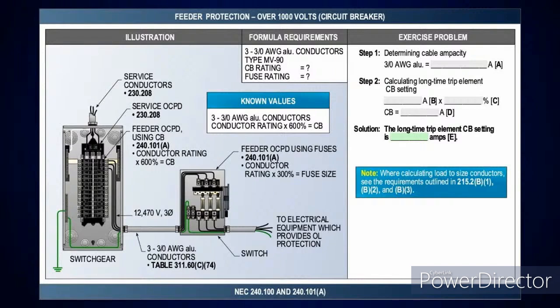Now, this one has 3 3/0 aluminum conductors. Once again, it's type MV-90. You're just going to go over, look at the table. You'll look at, in this case, table 311.60 C74, get your amperage, and then put your percentage on it, and then size your overcurrent device accordingly.